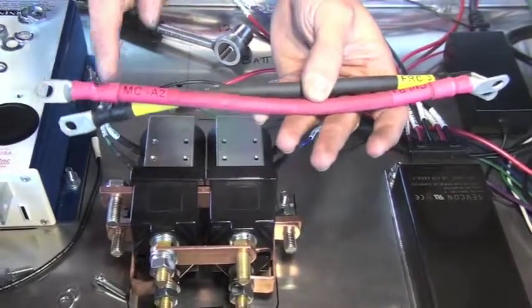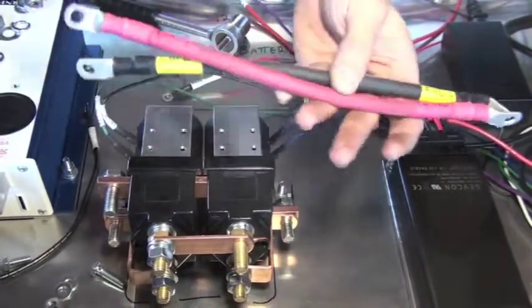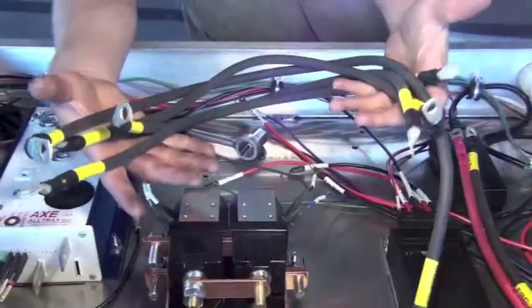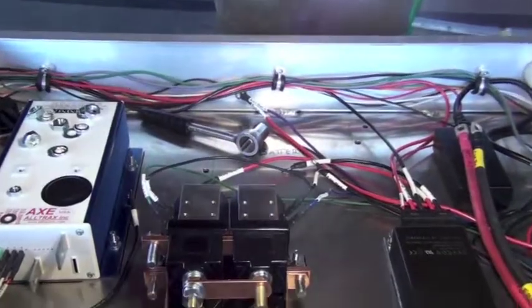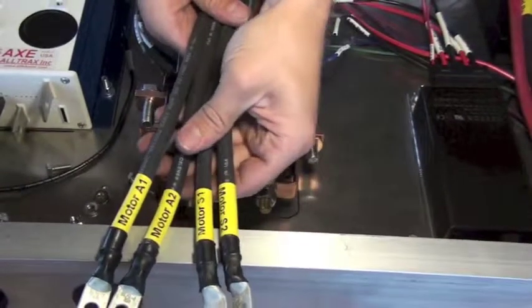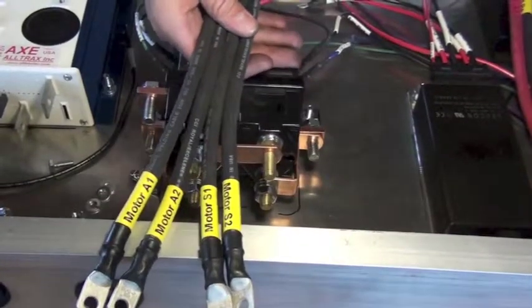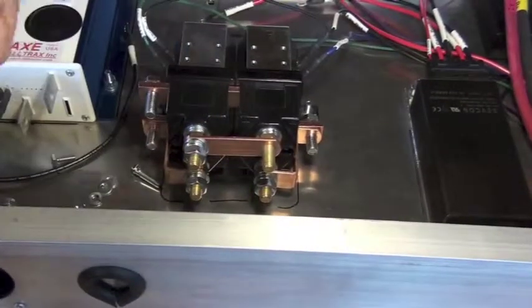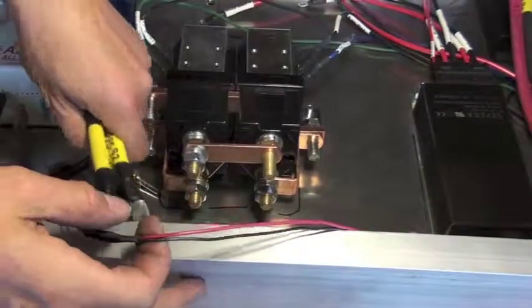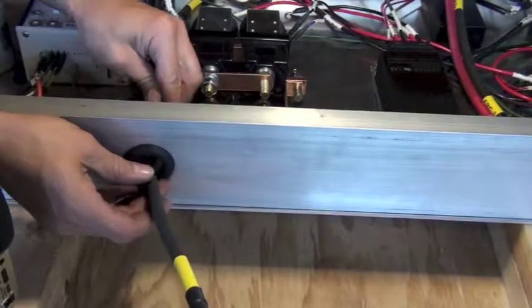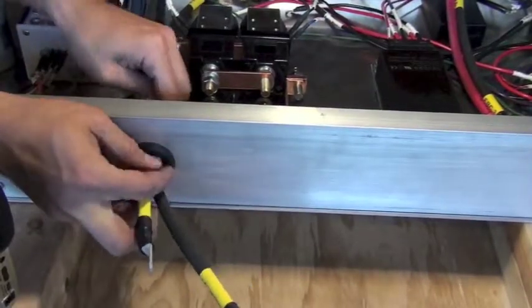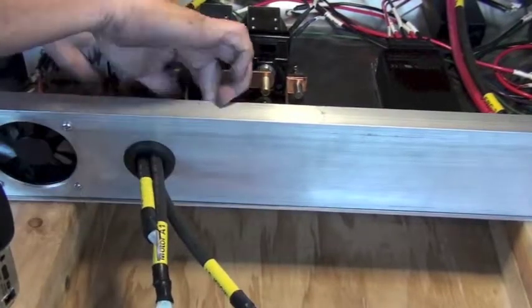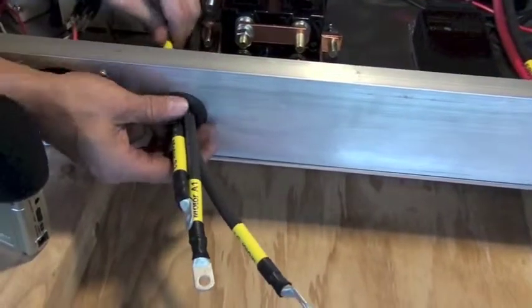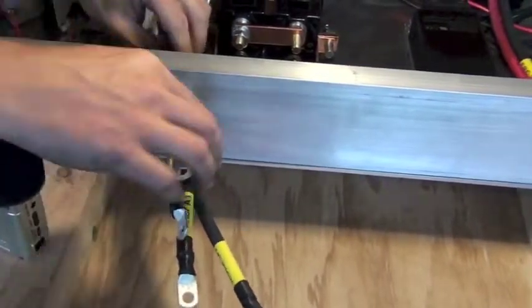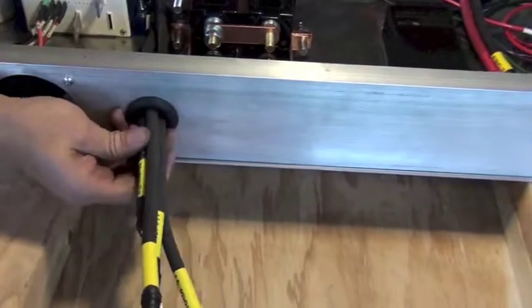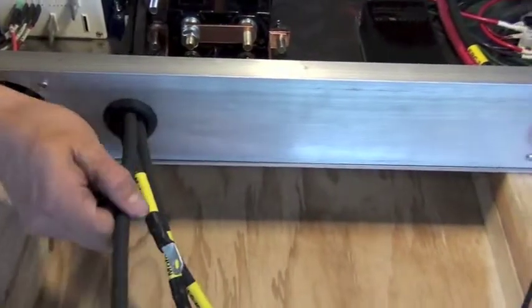Now we're going to install some thicker gauge cable. These 2 thick cables go between the contactors and controller. We also have some thicker gauge cable that goes between the box and the motor. So we'll take a look at the motor cables. We have motor A1 and A2, and S1 and S2, and these connect between components inside the box and the motor itself. So we need to have them exit the box through the back, and we're going to try to get them positioned such that the length of the cable inside the box matches right up with the component that it's mounting to. So first get all four started, get them through that opening, and then we'll size them to the points in the box that they need to be attached to.